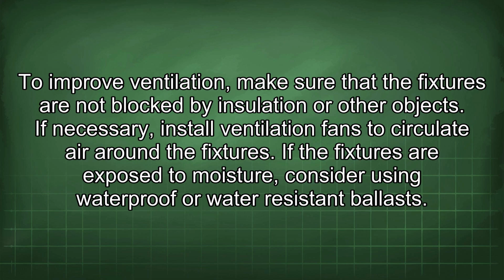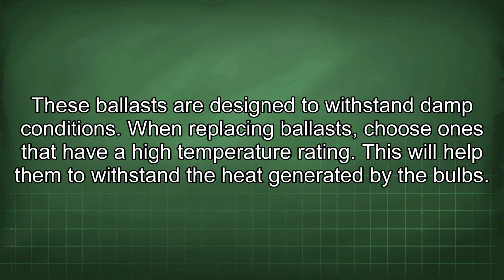To improve ventilation, make sure that the fixtures are not blocked by insulation or other objects. If necessary, install ventilation fans to circulate air around the fixtures. If the fixtures are exposed to moisture, consider using waterproof or water-resistant ballasts. These ballasts are designed to withstand damp conditions. When replacing ballast, choose ones that have a high temperature rating. This will help them to withstand the heat generated by the bulbs.